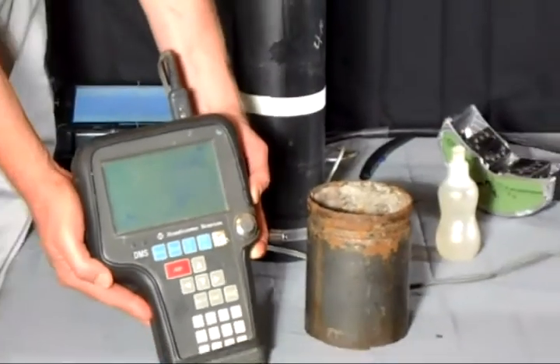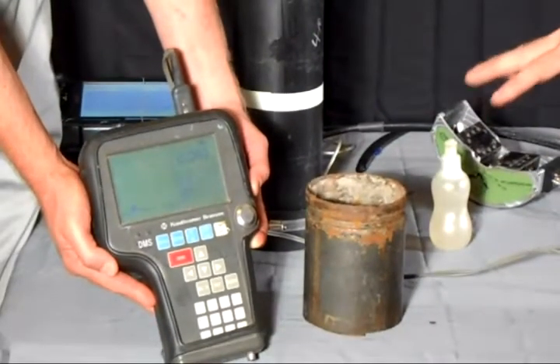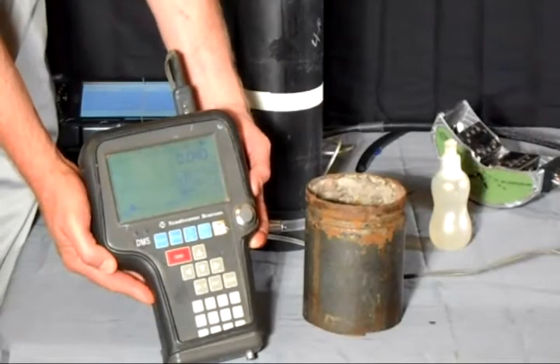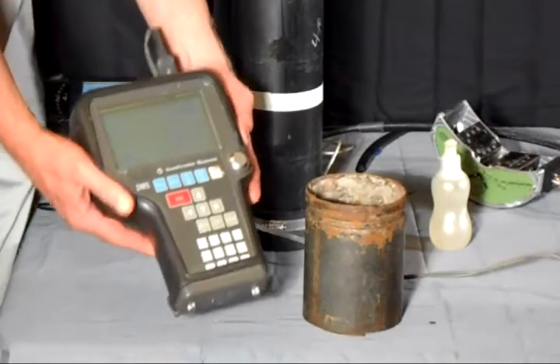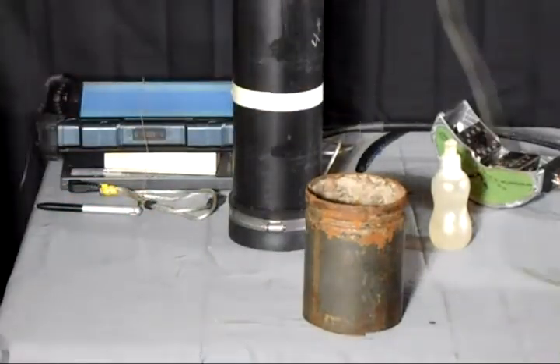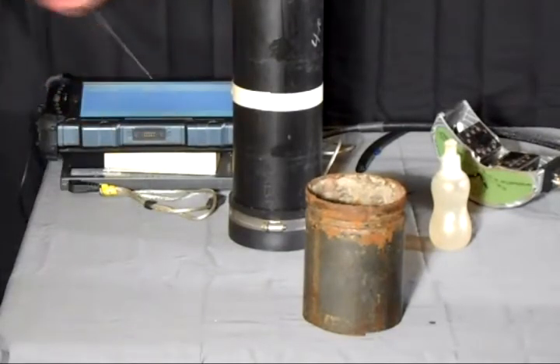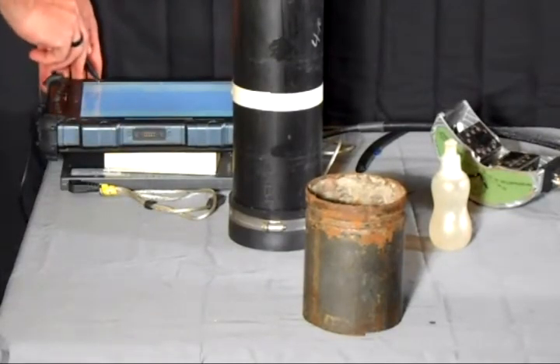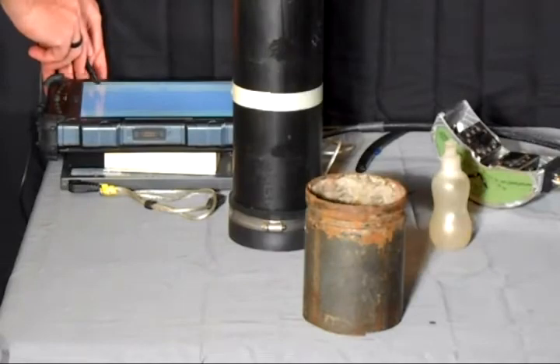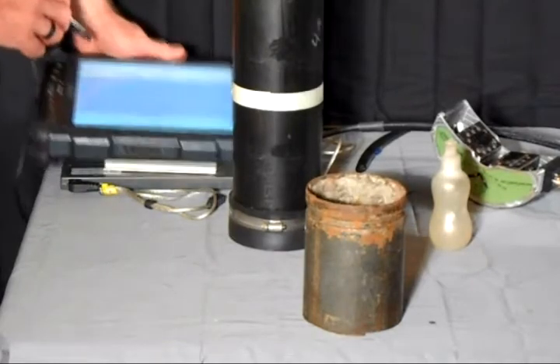But the important thing to note in regard to that is, as you can see, we really had to hunt around to find that specific area. So to really do an effective scan with this equipment on a large system would require sliding this transducer head over all of the equipment throughout the facility. So now we're going to run the same scans using localized guided wave.